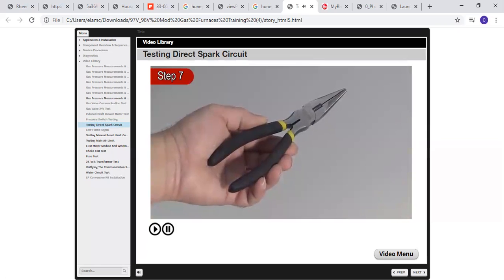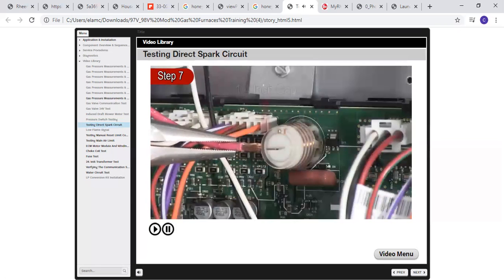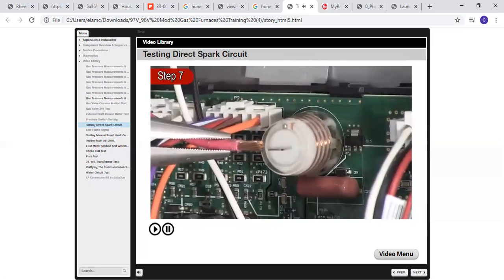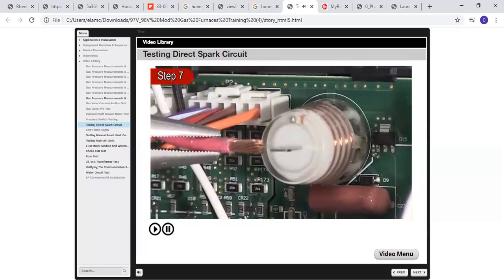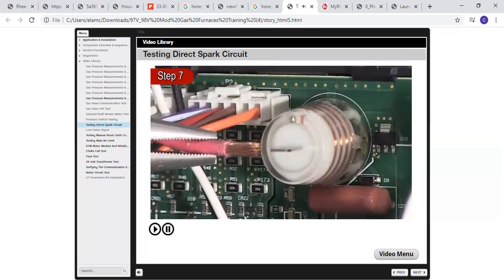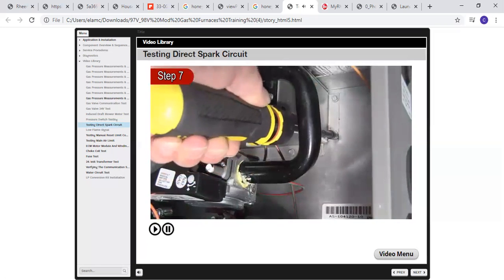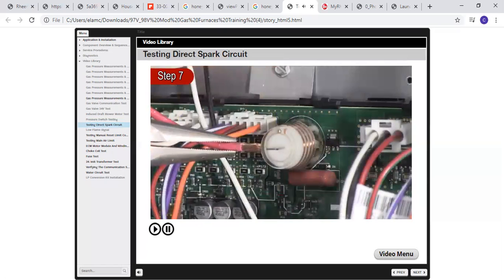Step 7. Using needle nose pliers with insulated handles, hold the stripped wire end about 1/4 inch from the furnace control spark igniter terminal. When the furnace enters a trial for ignition, the high voltage should spark from the terminal board to the end of the wire. If it does, check the burners for a good ground. If the furnace control board does not generate spark, replace the furnace control.